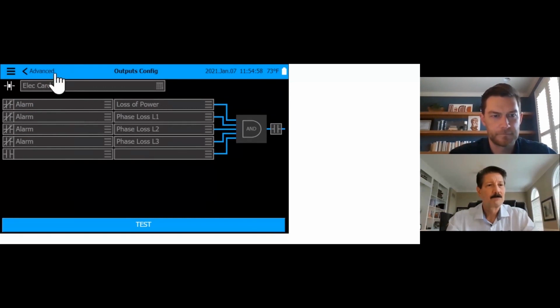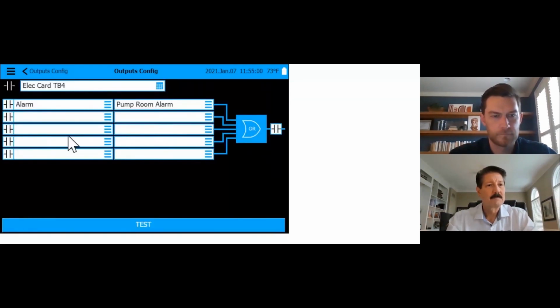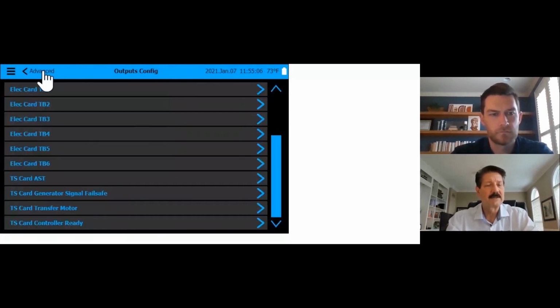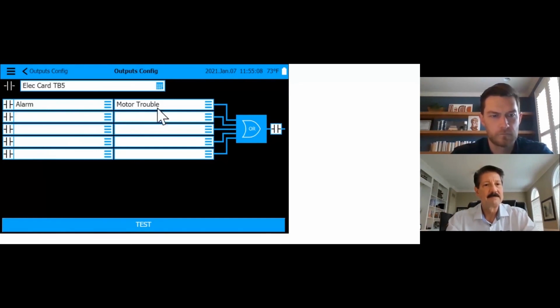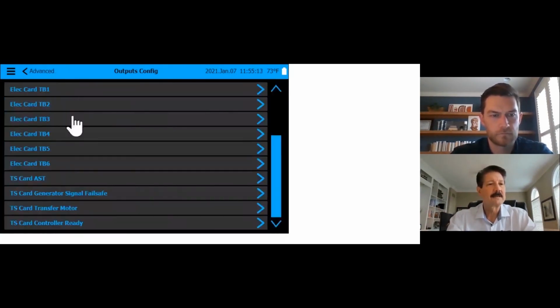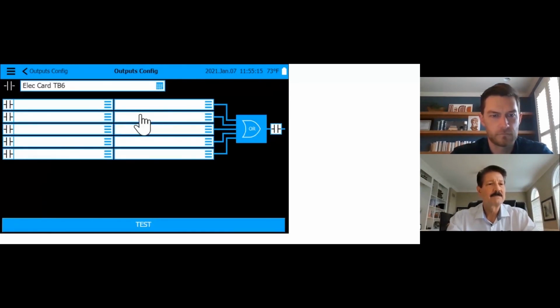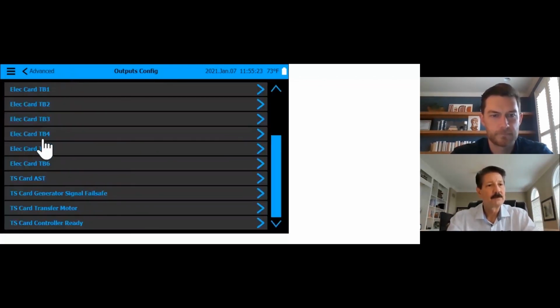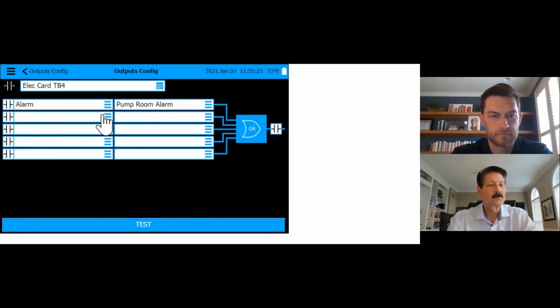Yep. Now, TB4, pump room alarm. I've covered that before. There's probably 4 or 5 different alarms that fall under that. TB5, motor trouble. About 3 or 4 alarms fall under that. And TB6 is a freebie. Unless it's a soft start, a GPS, this one won't be free, won't be available. But what you're able to do with TB4 or 5 is you can reprogram this if you want.